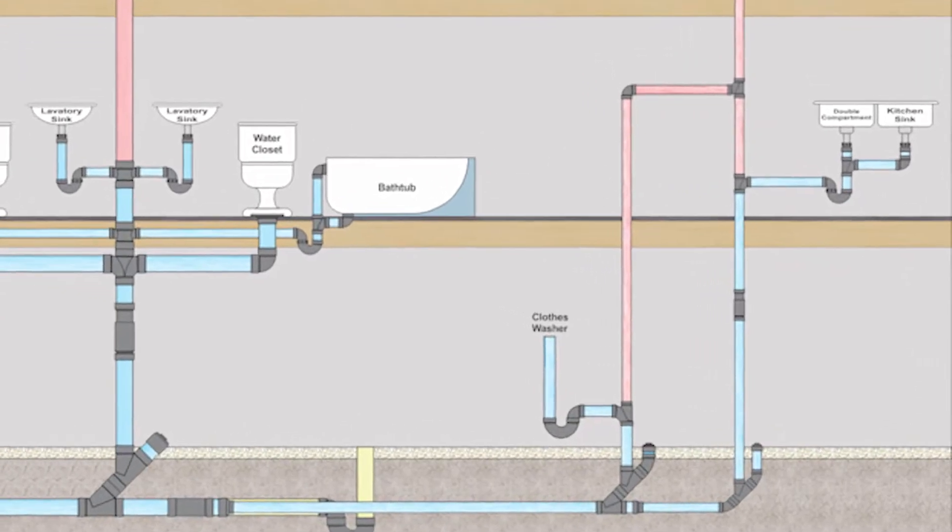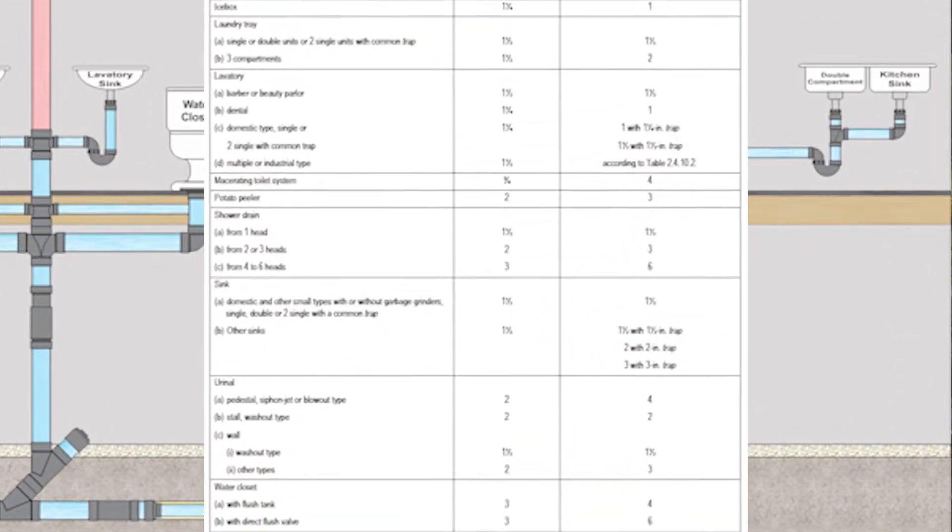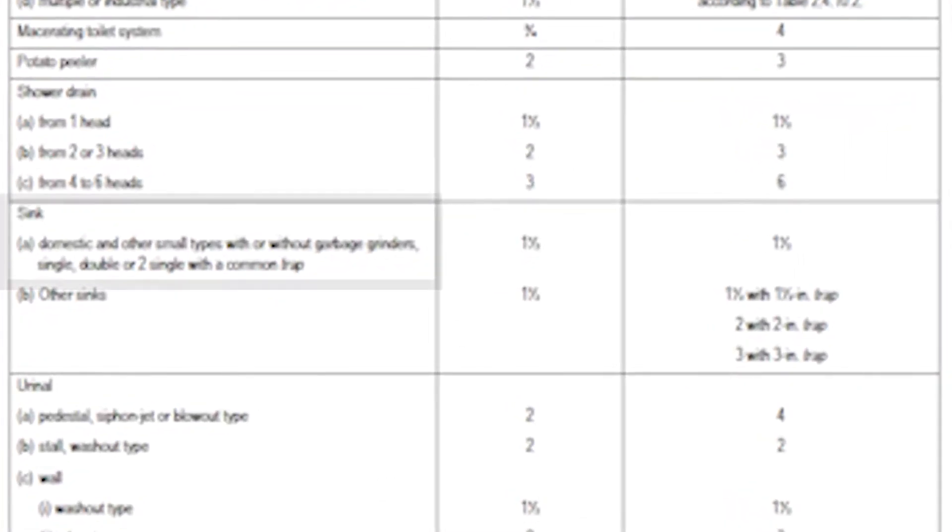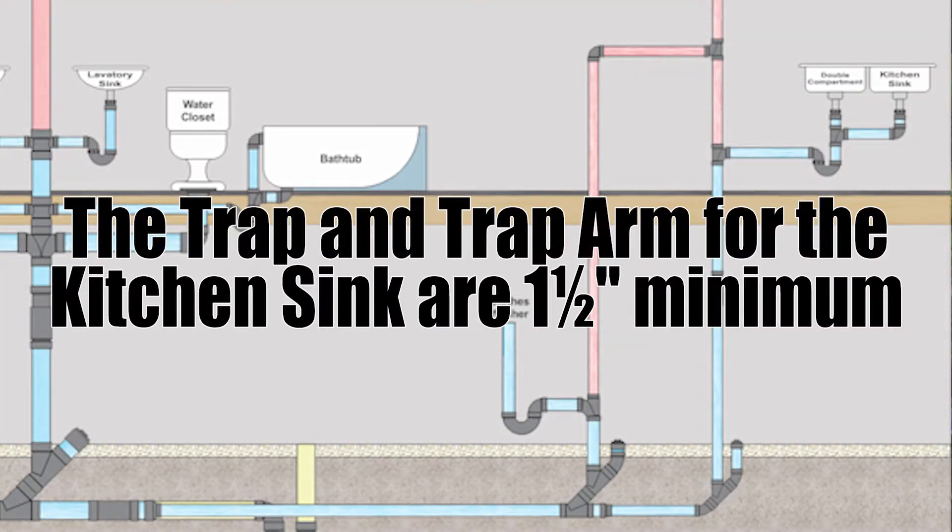Now if we look on the far right side on the main floor we will find a double compartment kitchen sink. In table 2.4.9.3 we need to locate sink domestic and other small types with or without garbage grinders, single double or two singles with a common trap. The minimum size of fixture outlet pipe is one and a half inches and with that we have one and a half fixture units. So the trap and trap arm serving that kitchen sink will be minimum one and a half inches.